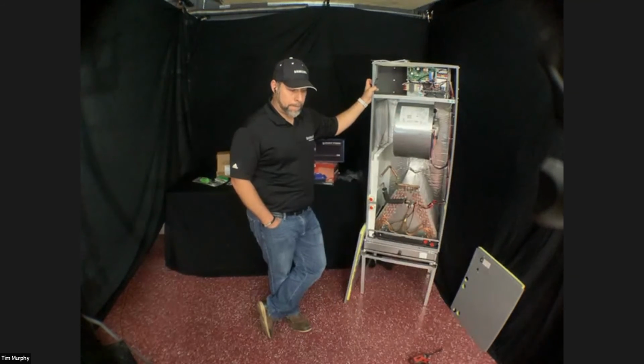So this can't be used as emergency heat when you wire that heat kit in. In other words, if there's a failure in the outdoor condensing unit, you can't turn this heat on as emergency heat. It doesn't operate that way. It's a supplemental heat strip only used in the event the heat pump can't keep up with heating the house. So it's very rare that you're ever going to install a heat kit in this unit. In fact, Heather, correct me if I'm wrong, but I don't even think we're planning on carrying those heat strips. They would be a special order item.